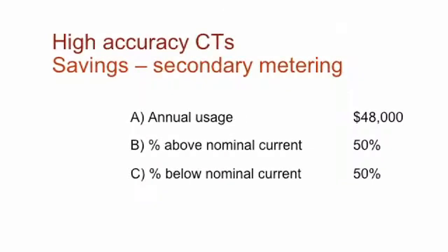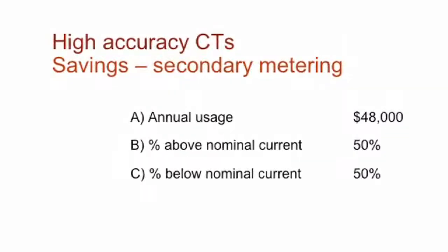One of the things that we're going to take a look at that's important, if you remember from the accuracy classes, as you fall down below nominal current, we said that the accuracy range was allowed to double around that on the IEEE standards. So the percent of time that you're above what we call nominal current, or what would be a high use time, and the time that you're below nominal current or a low load would be something similar. So for this example, we'll say 50% of the time we're above nominal current, 50% of the time we're below nominal current. So we'll just take an industrial application as an example. Maybe a small welding shop and fabrication shop.